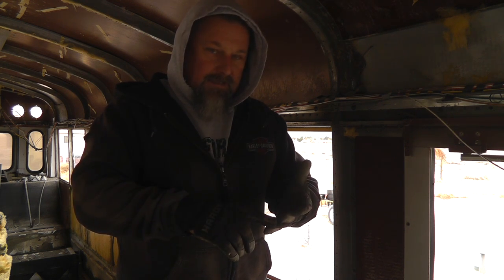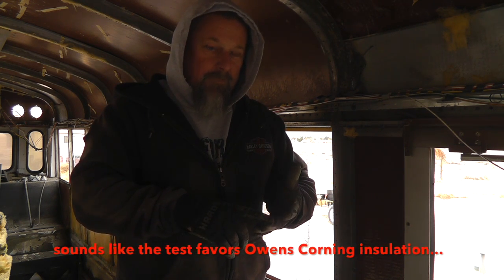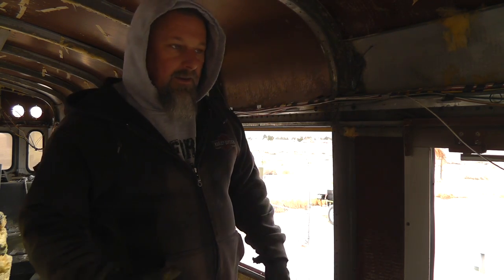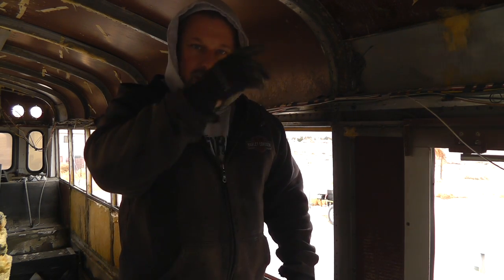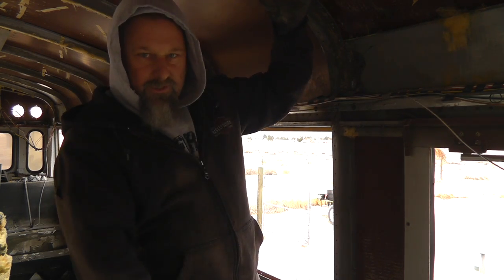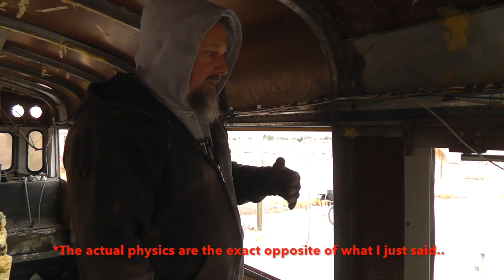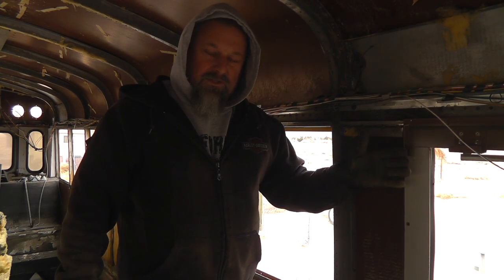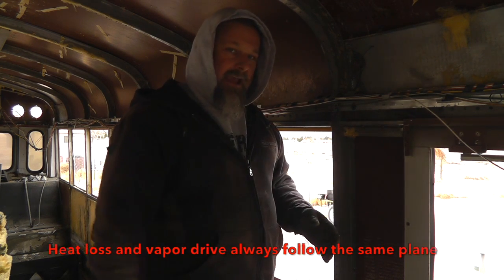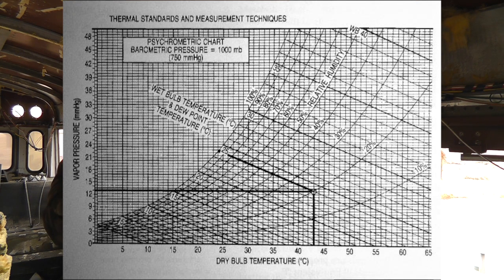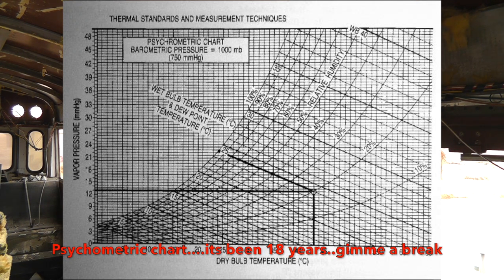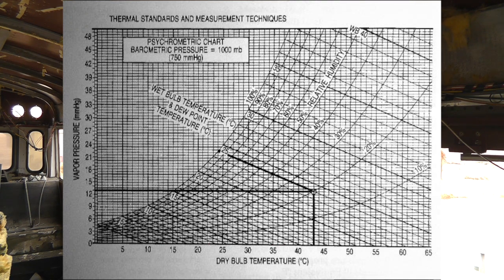The point I'm trying to make is it's only a 15-degree temperature difference — between 60 and 75 degrees — in a hermatically sealed test chamber, without any consideration for air infiltration, exfiltration, moisture content, or convective currents within a real wall cavity. When you stretch that wall cavity out to 8, 9, 10, or 12 feet, convective currents occur naturally inside that cavity because warm air rises and forces cold air down, and that cycle repeats. If there isn't an adequate vapor barrier on the warm winter side, moisture can be forced through the drywall into that cavity.